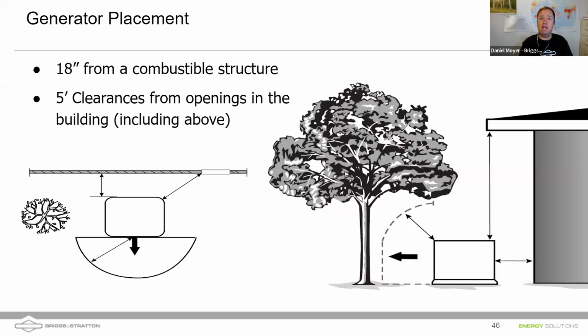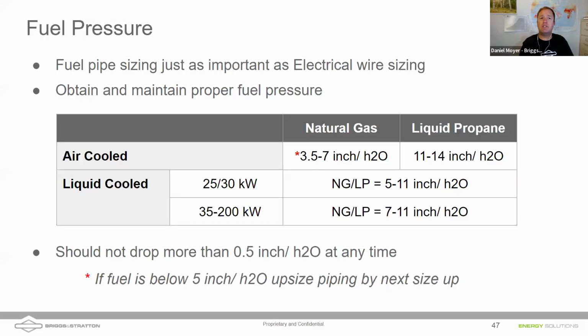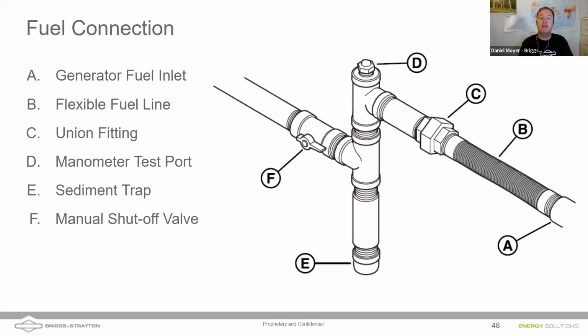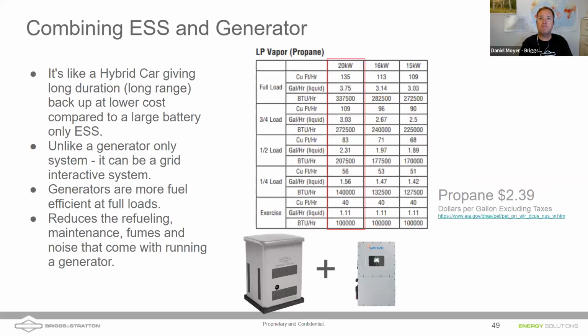Again, I'm going to skip ahead, but know where you can and cannot place the generator. One of the biggest things I see is fuel sizing, not making sure you do your fuel piping correctly on the generator. And then also making sure you get your drip leg on the fuel line into that generator correctly as well.